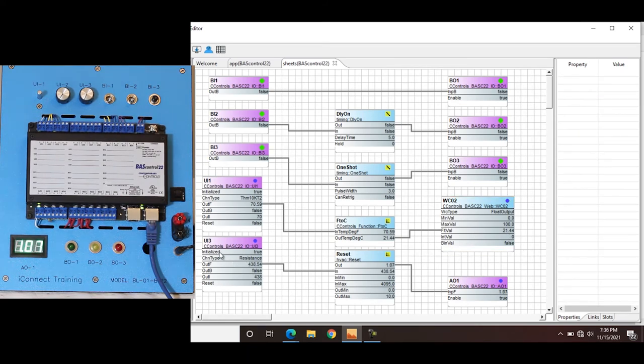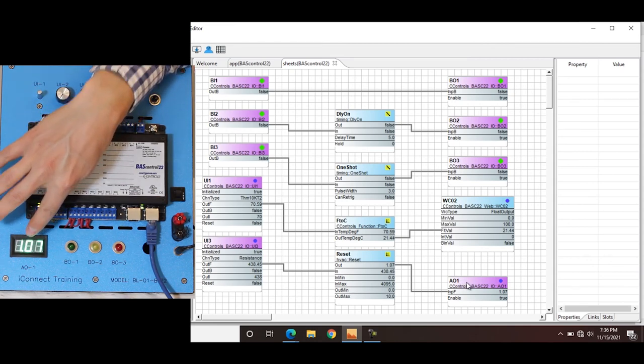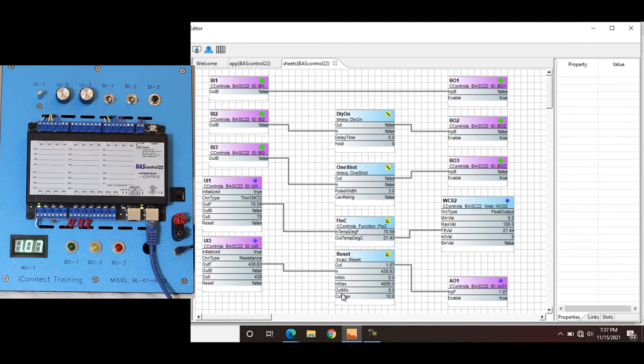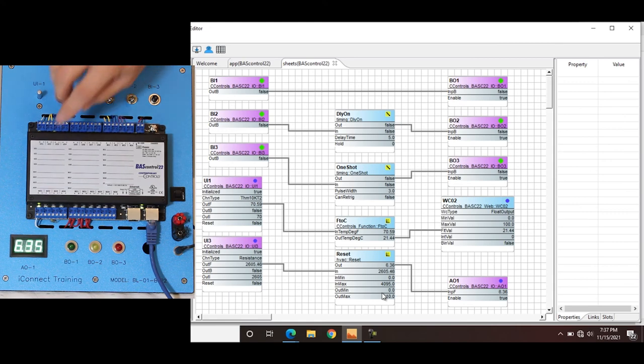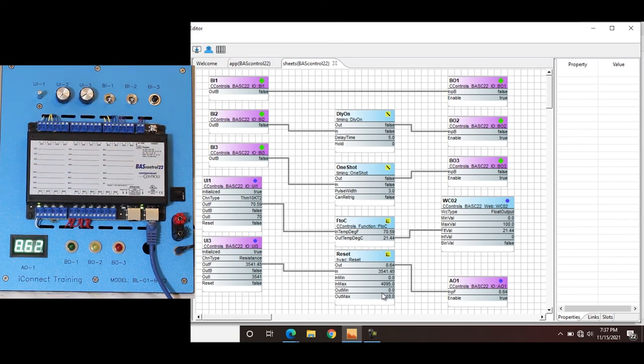For universal input 3, the out Fahrenheit right now is 438 degrees — this dial is very sensitive. This is feeding out to analog output 1, which is our voltmeter. Our out-min is zero volts and our out-max is 10 volts. If we adjust this, we can see the voltage increases. You can see on our voltmeter 8.64, which is translated through the reset. So this could be an air handler calling for a motor to ramp up — zero to 100 percent — and right now it's at 86.4 percent.